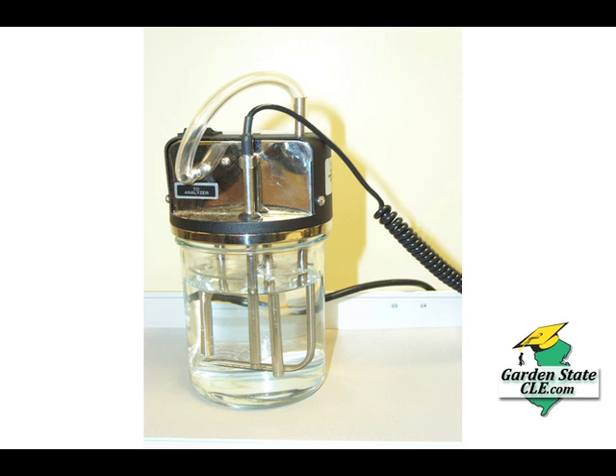Now this has a hose that hooks into the back of the Alcotest, and when a control test is done, it sucks the vapor out of there. It's the same way, instead of breathing in, it comes out of the CU-34, and it measures it. And you'll see the control test, and Lauren's going to go through the documents for you. And it has to come up between 0.095 and 0.105, even though it has a 0.10 solution in it, and then it's considered accurate. Not only is this accepted to plus or minus 5%, but the solution itself, when it's assayed and they say it's 0.10, is only held to 2%. And the heater in here is only held to 1.33%. So when I went to school, you aggregate those, you end up with 8.33. And that's the best this machine can ever be, consistently. Sometimes it can be even better, but not consistently.